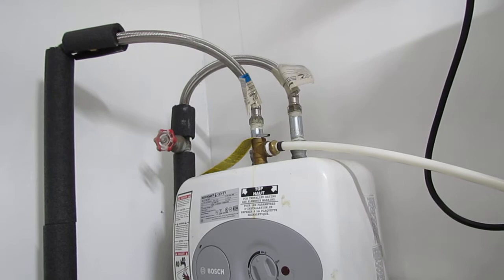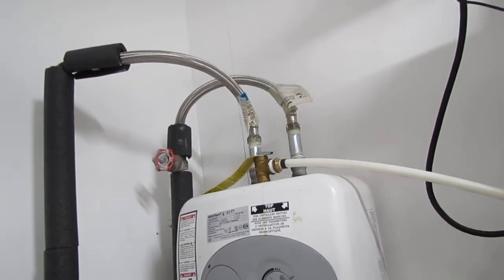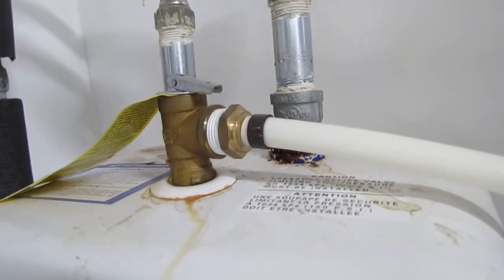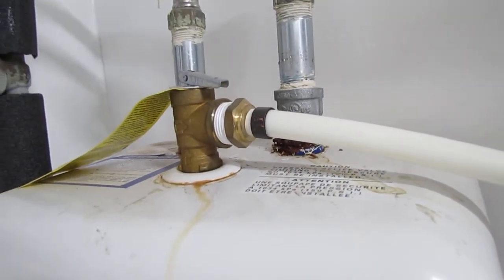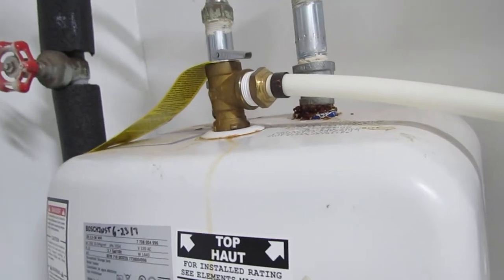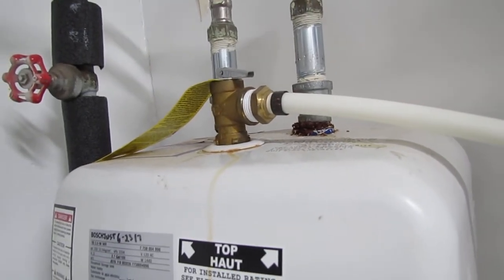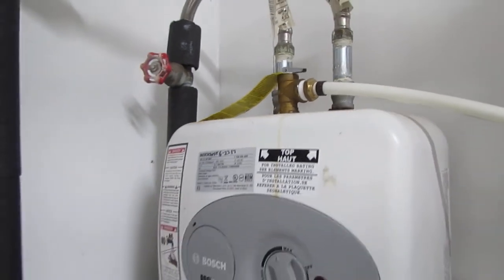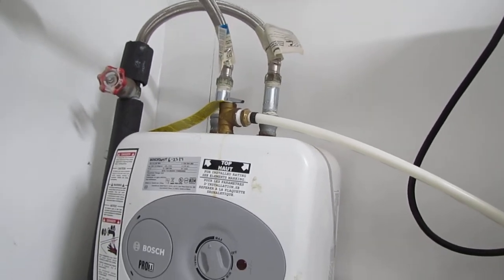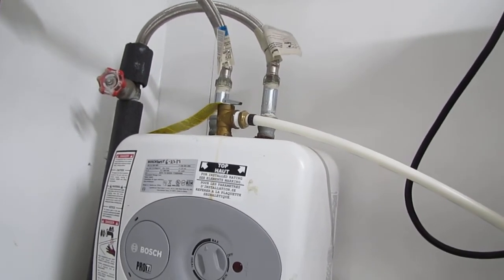You might think you already have that covered and assume that the T&P valve on there handles it — and you're partially right. That T&P valve is designed to pop off at extreme high pressure or extreme high temperature, but it's not designed to open and close on a continuous basis. It will fail from being cycled too many times. Also, a certain amount of pressure is required to activate the T&P valve, so thermal expansion inside the tank may not be enough to trigger it — but it is enough to cause the tank to fail.